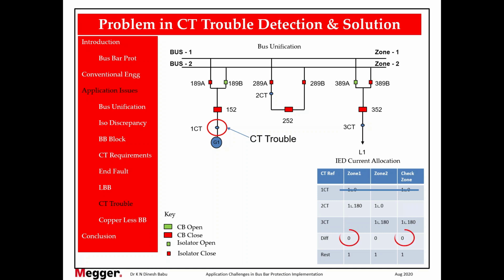So far, the same trip logic which Dinesh had discussed earlier would help. Now we can see here, because of the absence of this current, there may be some differential current, and this would be non-directional, not the directional one. So when we use this kind of trip algorithm, main zone directional, check zone non-directional, and bus PT under voltage, what will happen? The main zone directional in this example would become 1. But in reality, 99% of the case, this would be 0.